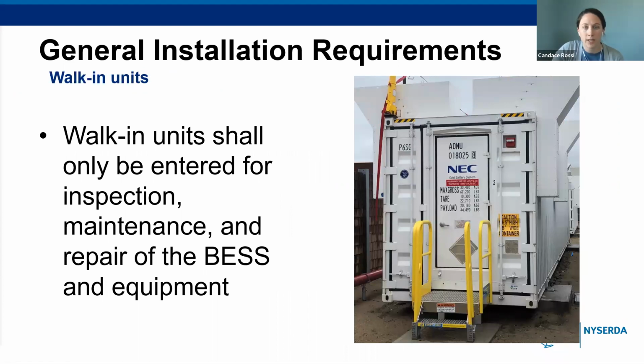So here I have our last general installation requirement. This is for walk-in units. These units are defined as an enclosure that is not for human occupancy, but can be entered for maintenance, replacements, repairs, and inspection. The risk of the containers presenting a life hazard inside during an event is significantly less than with systems located indoors, especially when compared to non-dedicated use buildings.